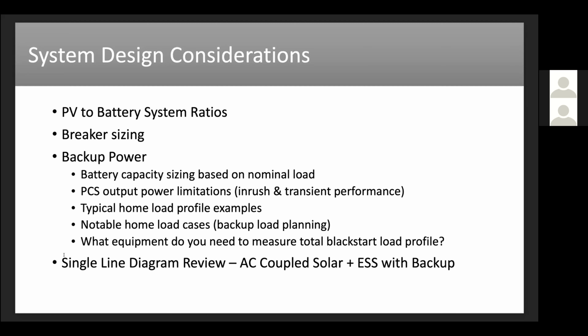And in planning that, you do need to take some measurements. And when you do that, what equipment do you need in order to measure total black start load profile for that new backup loads panel? As with many things, and most importantly with planning a battery system that does provide backup services, some planning will pay you tenfold on the back end, with avoided nuisance trips and truck rolls to do service calls if you overload that backup loads panel.